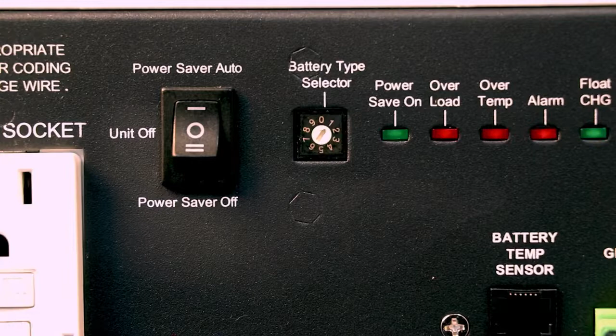For example, if I wanted to change it to a gel cell battery, I'd open the instruction manual, look at the settings, and see that a gel cell battery is setting number 1. So I take a small screwdriver and turn it to setting 1. Now the charger is set to a gel cell battery, and it'll adjust the voltage settings to charge the battery correctly.